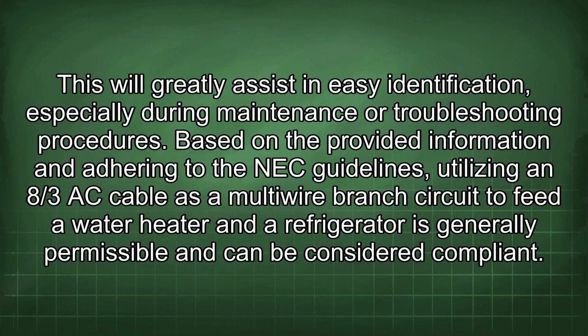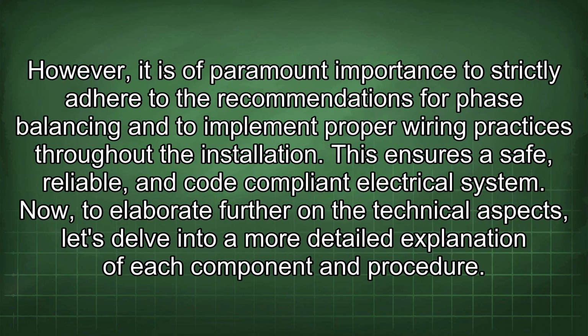Based on the provided information and adhering to the NEC guidelines, utilizing an 8/3 AC cable as a multi-wire branch circuit to feed a water heater and a refrigerator is generally permissible and can be considered compliant. However, it is of paramount importance to strictly adhere to the recommendations for phase balancing and to implement proper wiring practices throughout the installation. This ensures a safe, reliable, and code-compliant electrical system. Now, to elaborate further on the technical aspects, let's delve into a more detailed explanation of each component and procedure.